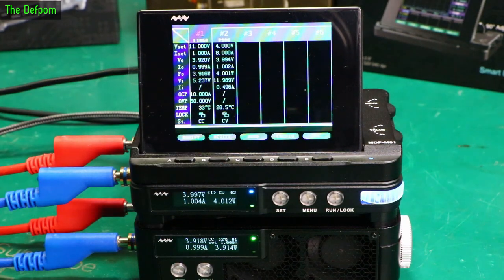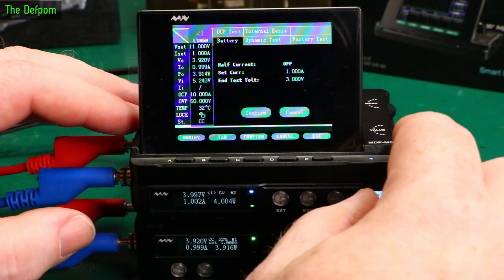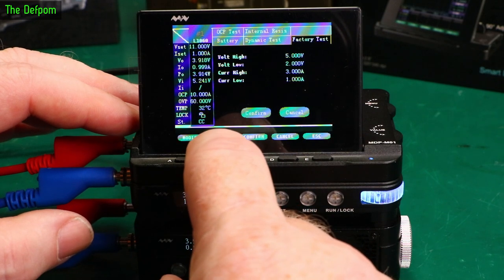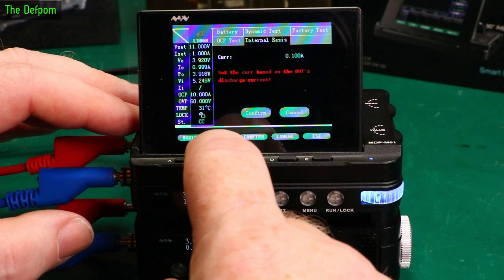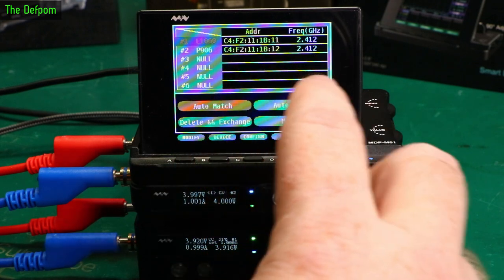There's more options in here - different tabs. It's got a cycling mode, factory testing, overcurrent protection testing, internal resistance. And there's a Config section - this is for doing wireless settings. You've got the loads and then the power supply listed, and you can actually reorganize these and change the sequencing, though I think you have to do it on a computer.